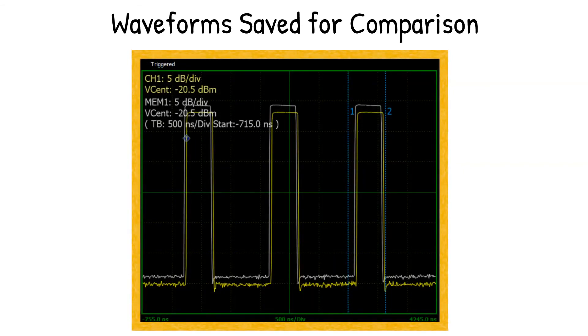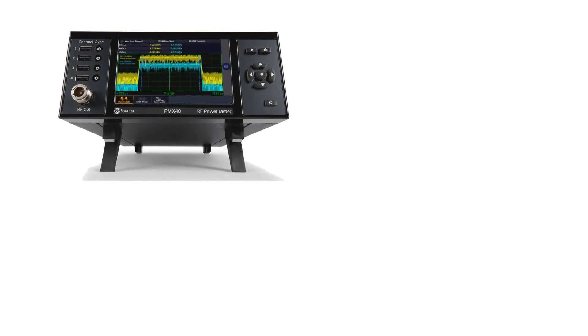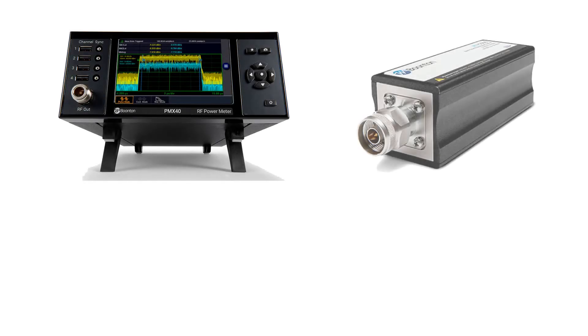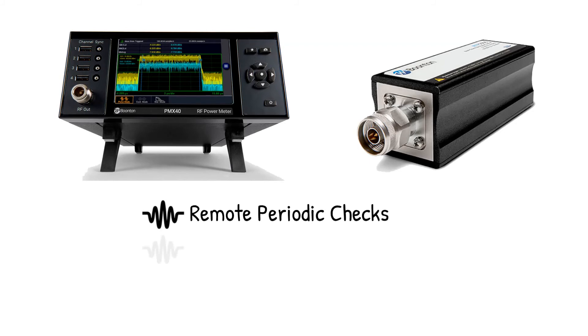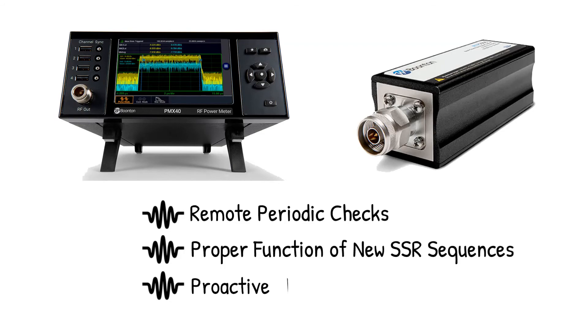Pulse waveforms can also be saved and recalled for later comparison, which may show power level changes and response delays over time. If using the PMX40 and associated sensors, this comparison can be used to perform remote periodic checks, ensure the proper function of new SSR sequences, and support a more proactive monitoring approach for SSR systems.